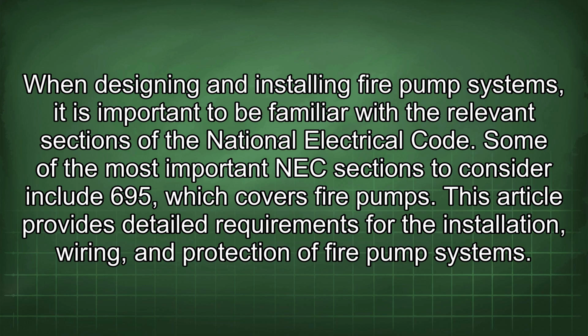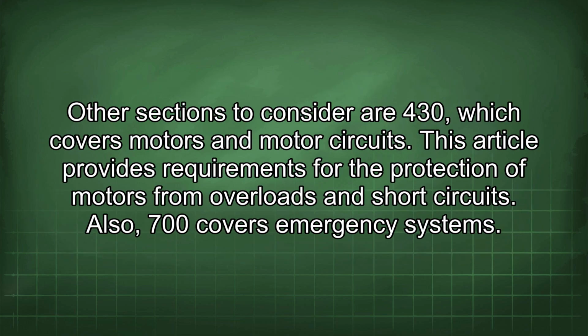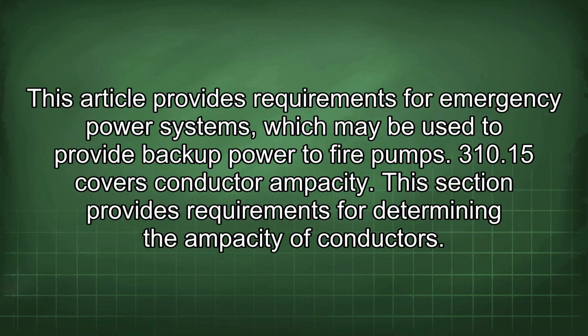Now we will discuss specific code sections to consider. When designing and installing fire pump systems, it is important to be familiar with the relevant sections of the National Electrical Code. Some of the most important NEC sections to consider include 695, which covers fire pumps. This article provides detailed requirements for the installation, wiring, and protection of fire pump systems. Other sections to consider are 430, which covers motors and motor circuits. This article provides requirements for the protection of motors from overloads and short circuits. Also, 700 covers emergency systems. This article provides requirements for emergency power systems, which may be used to provide backup power to fire pumps.